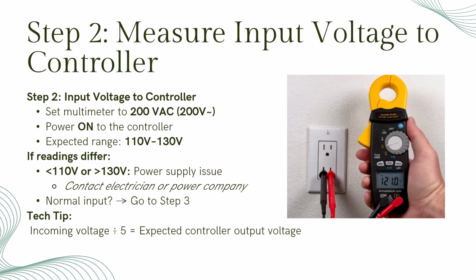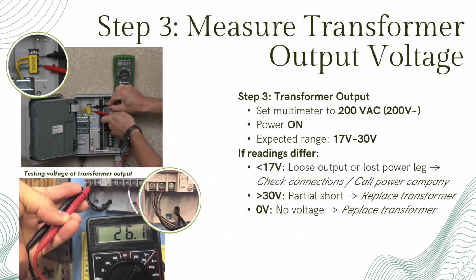You can expect that your controller output voltage is 1/5 of your incoming voltage. Step 3 is to check the transformer output. This is where 120 volts is stepped down to about 24 volts for the irrigation system. If your readings are below 17 volts, check for loose connections or a lost leg of power. If they're above 30 volts, that usually means a partial short, time to replace the transformer. A 0 reading means the transformer has failed completely, and your next step is to install a new one before retesting.